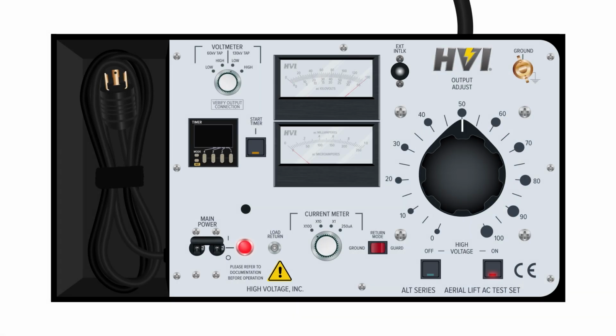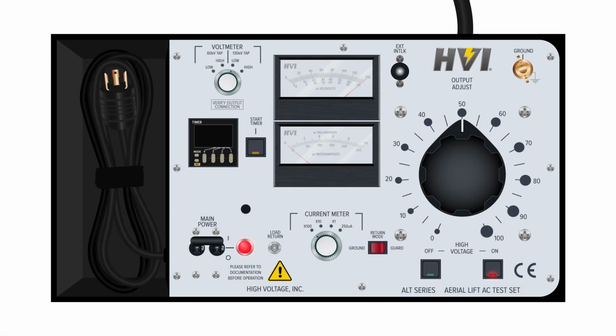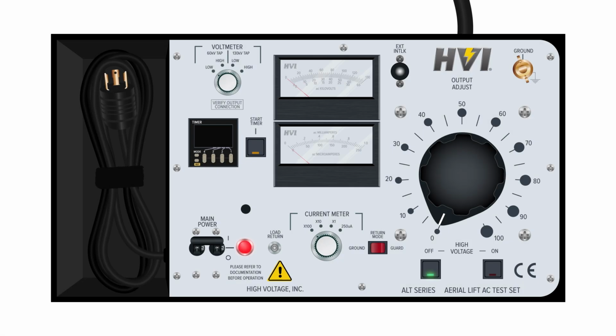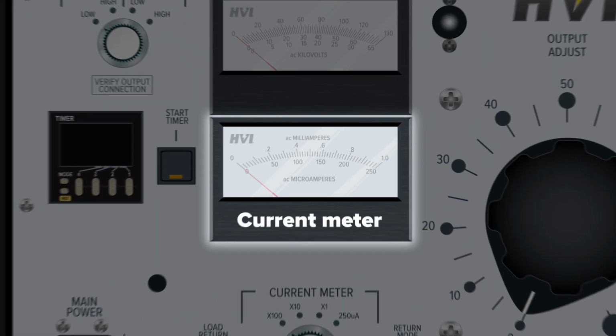The middle scale is also used when the switch is set to low range for the 130 kV tap, for voltages up to 60 kV. When the switch is set to high range for the 130 kV tap, for voltages up to 130 kV, the meter is read from the very top scale. The current meter is located in the center of the control panel.